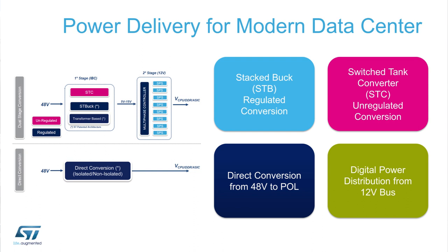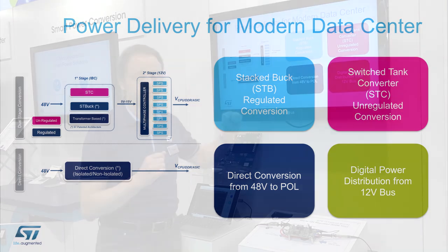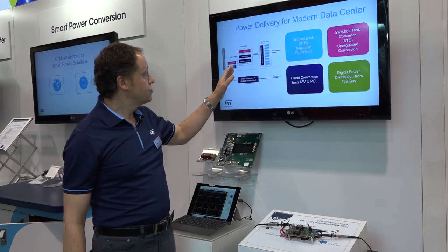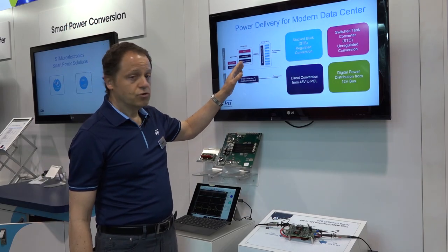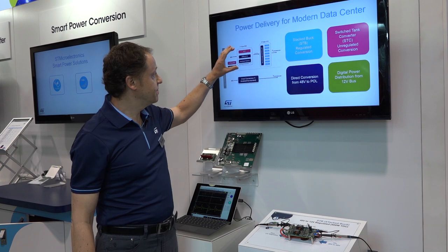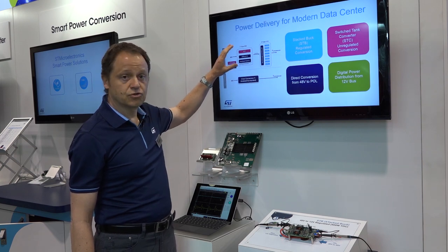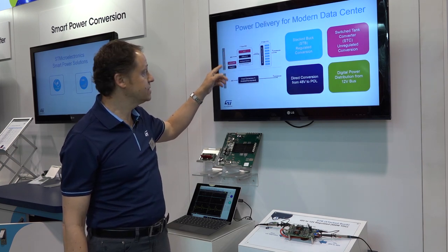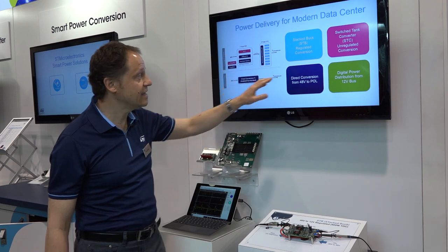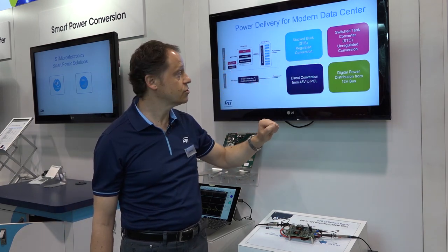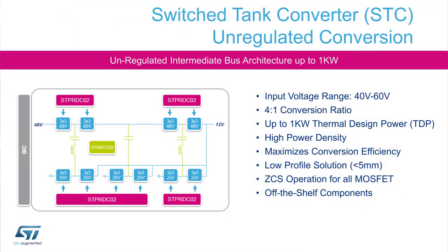The second class of products is a direct conversion from the 48 volt down to the point of load. For the two stage approaches we have different architectures: we have unregulated architectures that are based on STC switched tank converter, and this switched tank converter implements a fixed conversion ratio — the most popular is 4 to 1, so that we go from 48 to 12 volt.